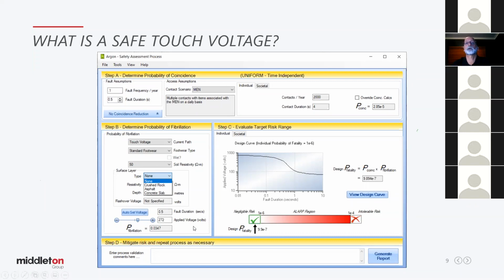So this bit of software here, from our inputs, can tell us what allowable voltage the standard allows the designer to work to, and indeed that the likelihood of fatality is less than 1 in a million. That's what we aim for. Society accepts less than 1 in a million from a risk perspective.